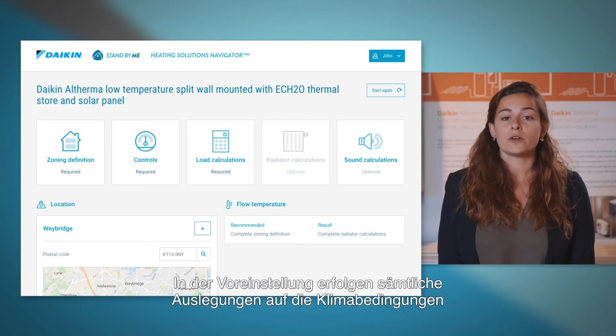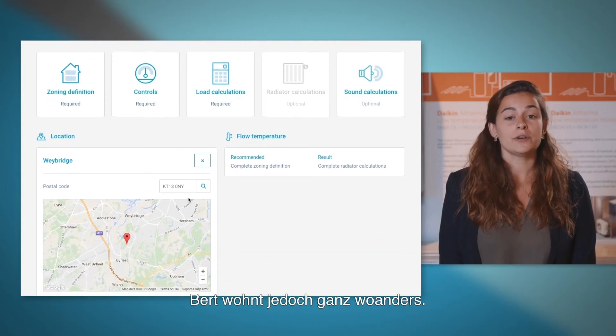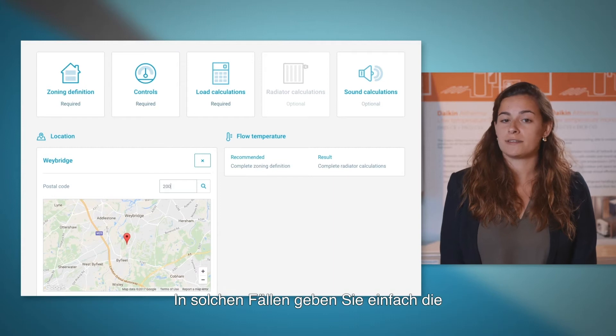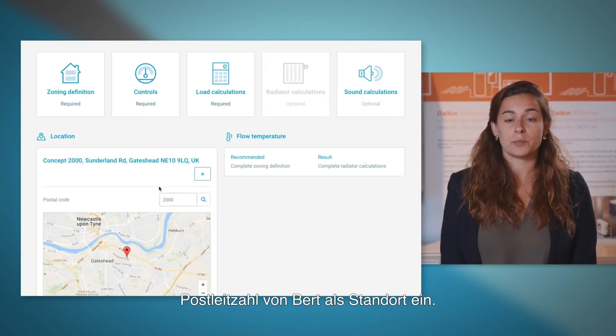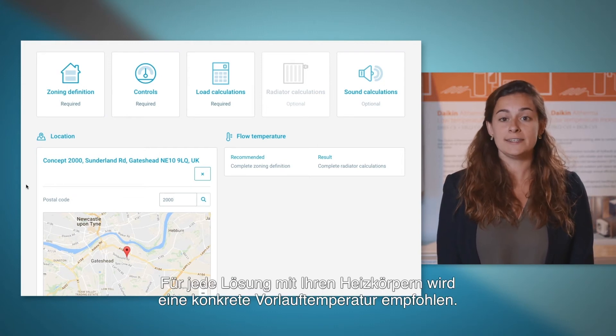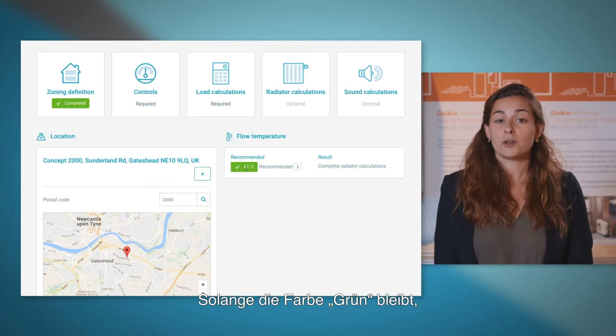By default, all sizing is based on the climate conditions for the address of installer John. However, Bart does not live near where John is based. It is then possible to change the location by entering the postal code of Bart's home. Each solution and its heat emitter choice has a recommended flow temperature. As long as the color remains green, you can expect your system to be running optimally.